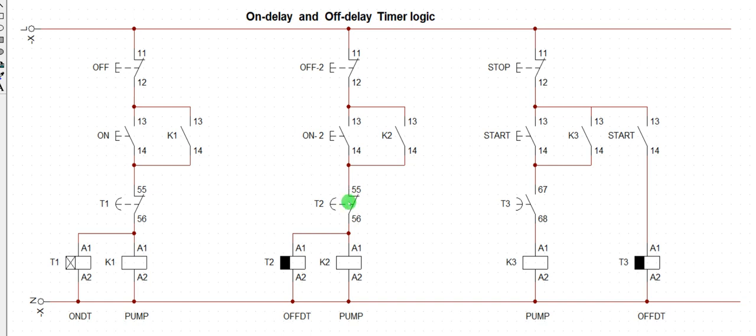Now, this one is normally closed. Once I energize this coil, here will open. Once I de-energize the coil, the relay starts counting. When the time of counting is completed, the contact will change state the second time. So the transition of this one happens 2 times. It will change immediately when energized. It will also change when de-energized, after counting is completed.